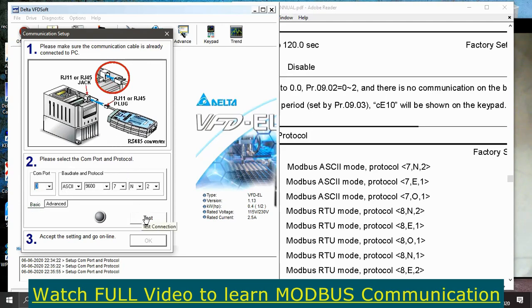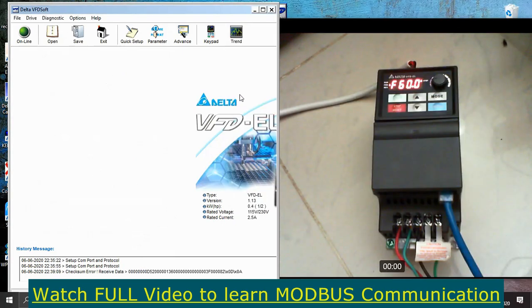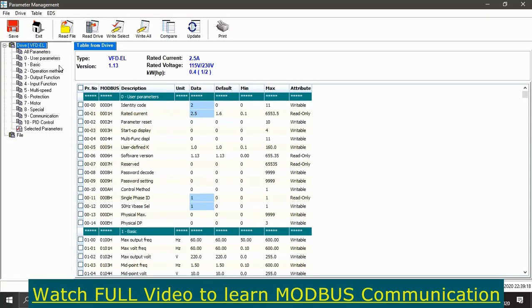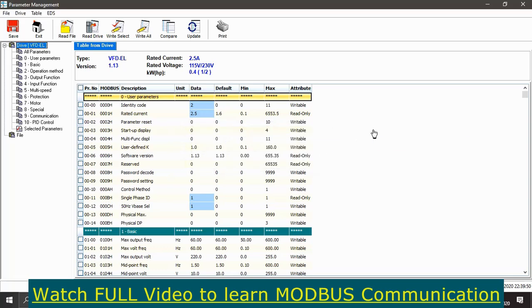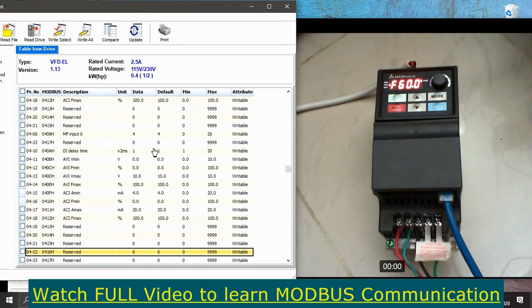Now I can see the green connected button — my VFD is properly connected with the software on my computer. To download parameters, go to the Parameter menu and click Read Drive. This downloads all parameters from the VFD to my computer. Now I can see all the parameters currently inside the VFD, and I can change them here and upload back to the VFD.